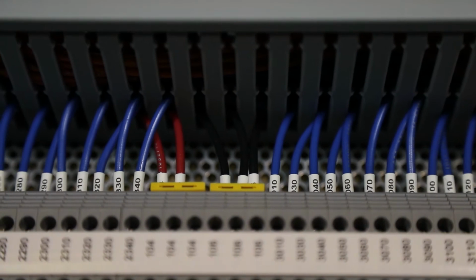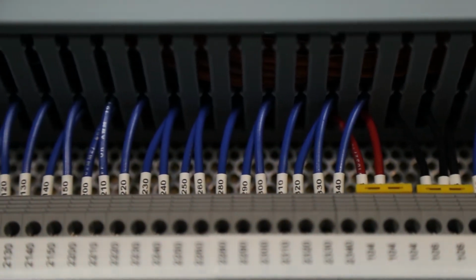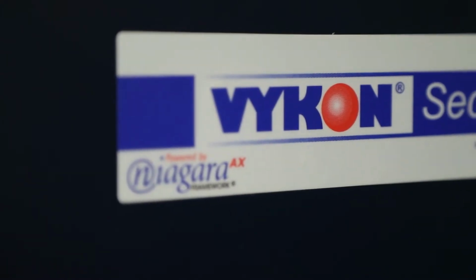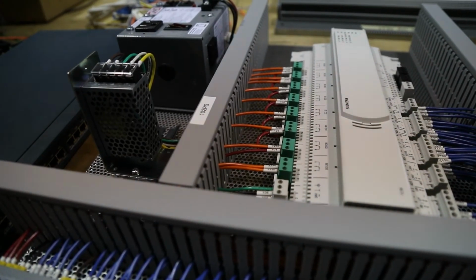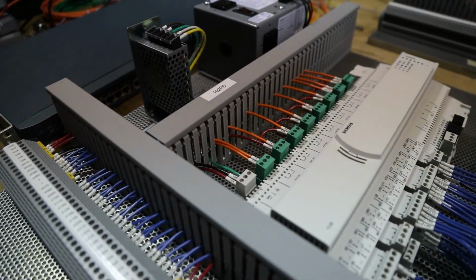So one of the problems that we'll run into with an aging system is the proprietary components. If a component does fail, either that source is no longer available, or the manufacturer doesn't make that particular component anymore. A lot of manufacturers do sunset a product, and then after that there's no more availability. They don't buy the chipsets anymore, they don't make that exact component.